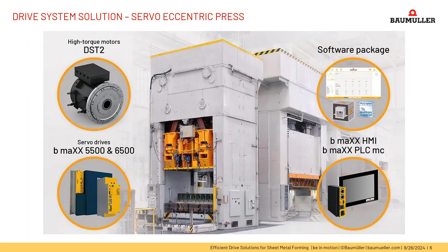This 3,000-ton press requires a lot of power. In this case, there are 3 DST2 high torque motors being used. Each motor has 4 windings that are controlled by 4 power modules synchronized together. 2 of the drives are operating in a shared DC link. Each DC link is connected to an active front end. The DC link capacitors are being used to reduce peak loads by storing and reusing regenerated energy.